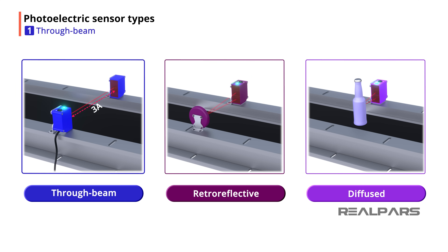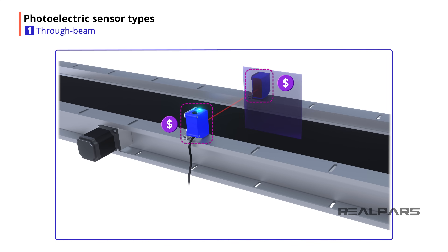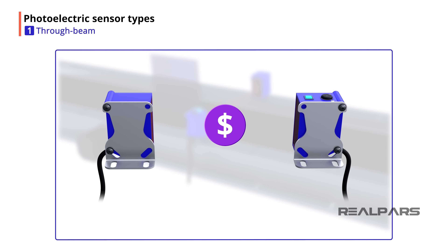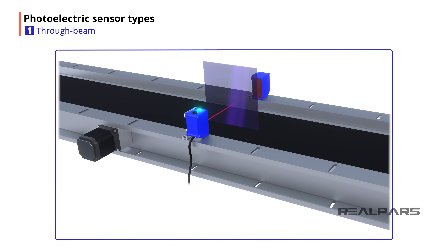Through-beam photoelectric sensors have a longer detection range than retro-reflective and diffused photoelectric sensors. This is because the light only has to travel in one direction to get from the emitter to the receiver. Some disadvantages of using a through-beam sensor are: they cost a little more, they require more room to mount correctly, and they do not detect thin clear objects well. Through-beam sensors cost more because they have two components that require two cables and two mounts, which is also why they take up more space. They do not detect thin clear objects because the light can travel straight through the object to the receiver.